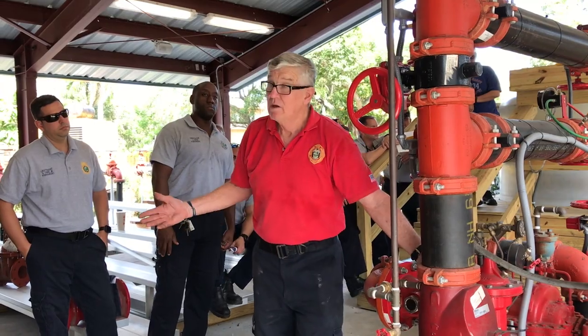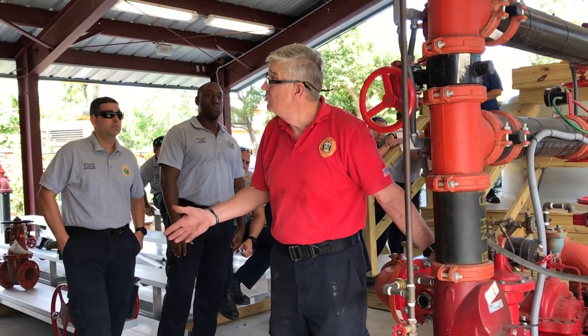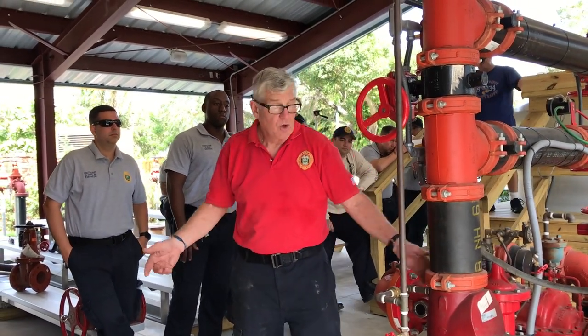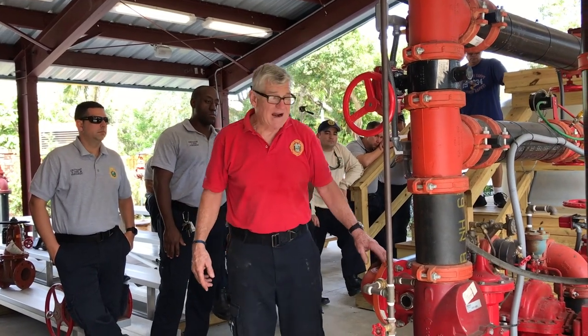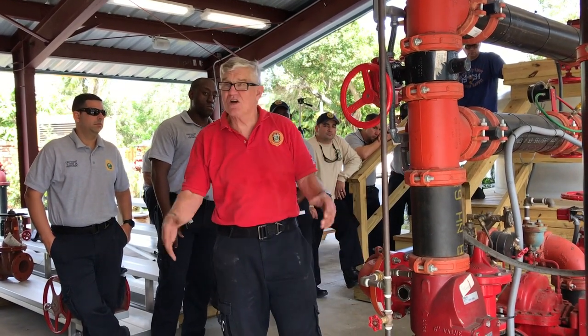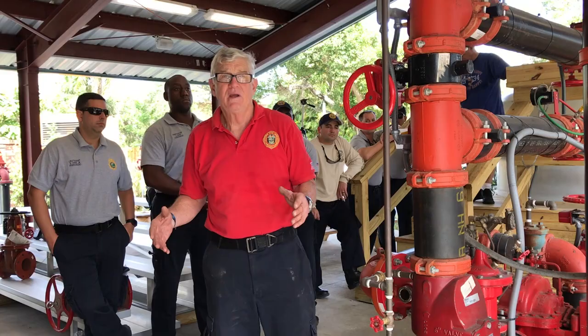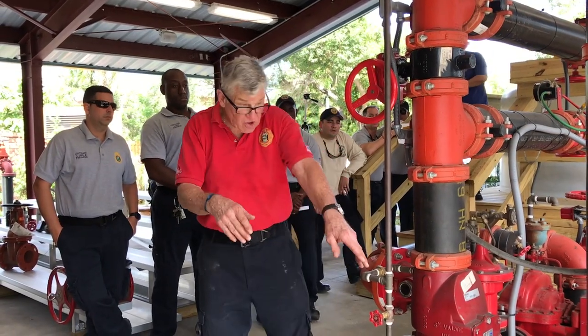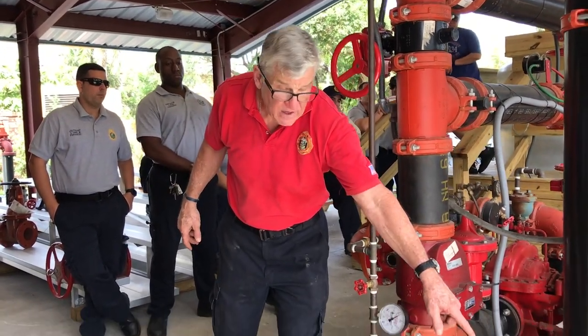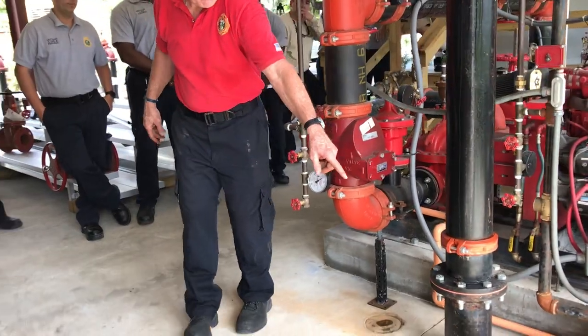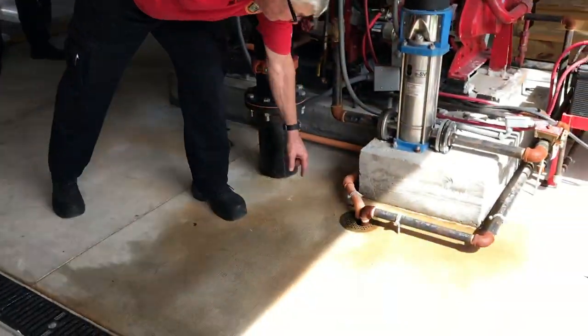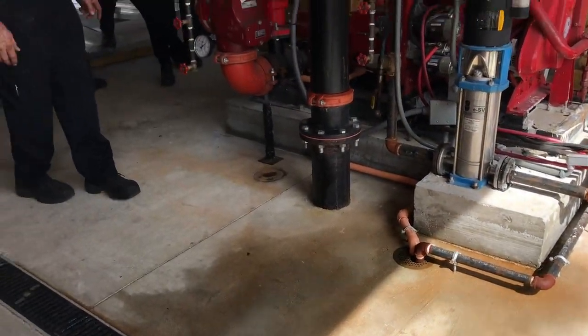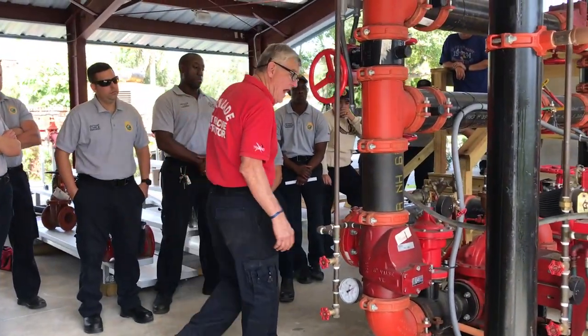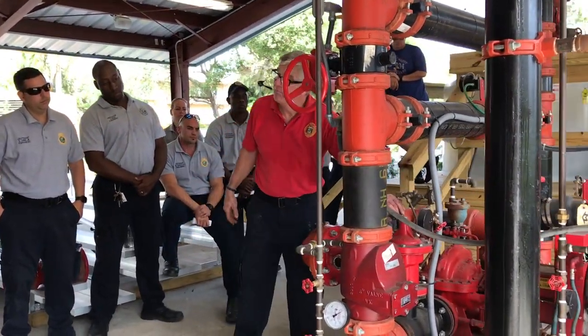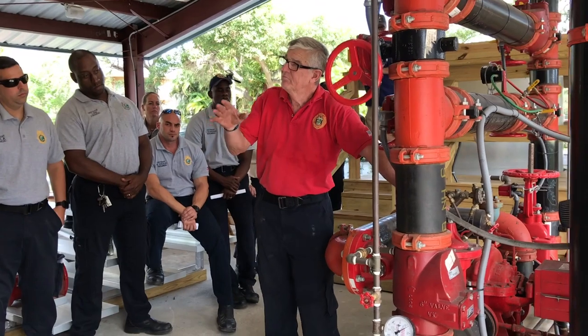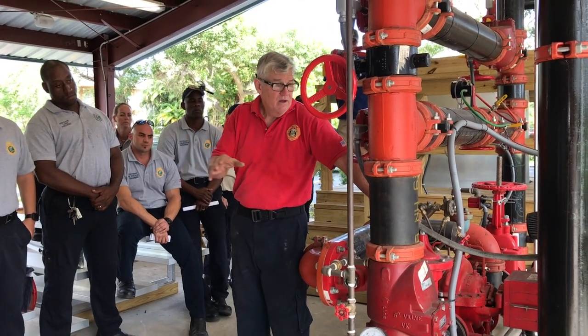Now, we've got to do something to relieve that pressure. What do we have? On an electric pump, you have a casing relief valve. It discharges water onto the floor at a floor drain. This was an electric pump right here. There is a relief valve on this diesel pump, but it's for a different reason.